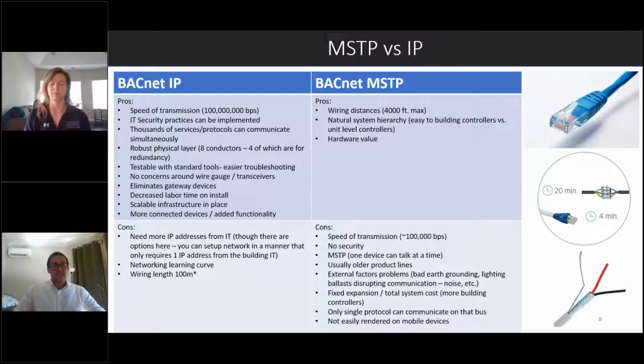BAS systems are no longer set up like they originally were. The intentions in 1995 were for it to be its own standalone system separated from IT. There's a lot more interaction with IT at this point, and you really want a system that cleanly works with IT systems and maintains the same level of security as the IT side of things. There's a lot more security available over IP communication as opposed to serial communication, where along that serial chain there's next to no security. So it's very important to have that available, and it's going to become more and more prevalent.